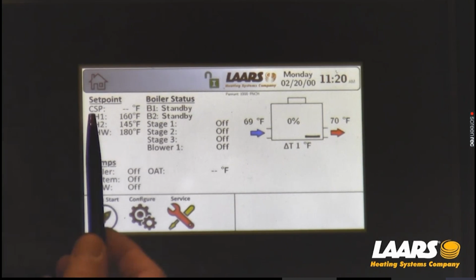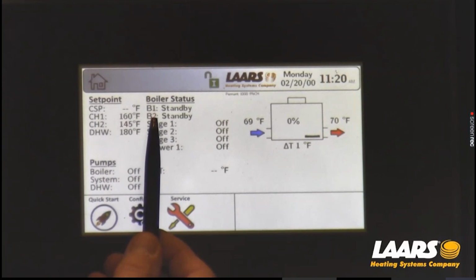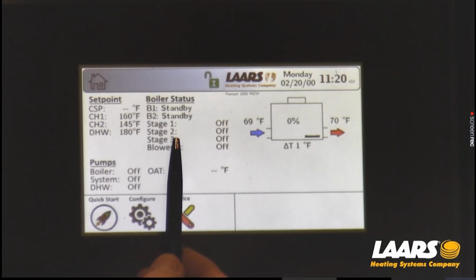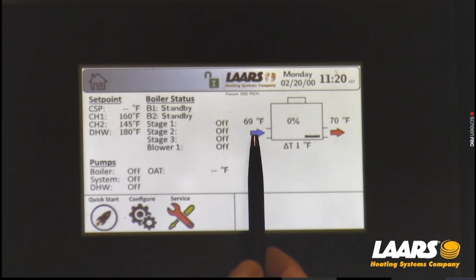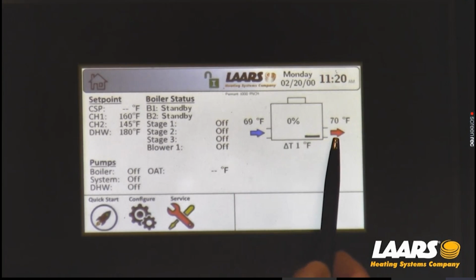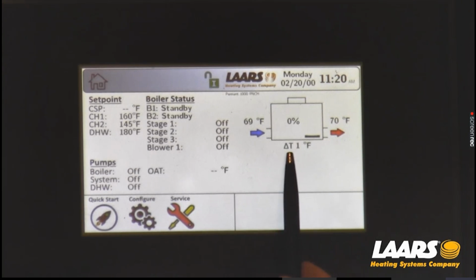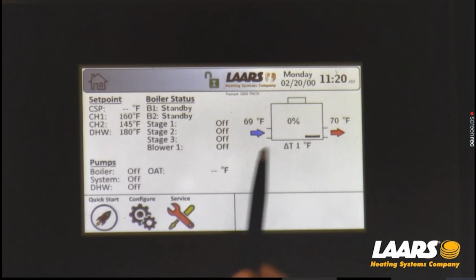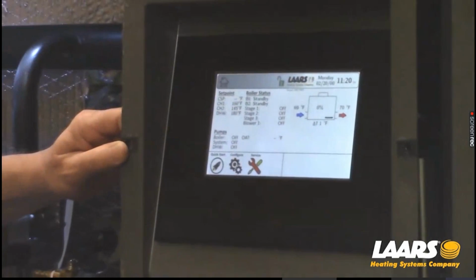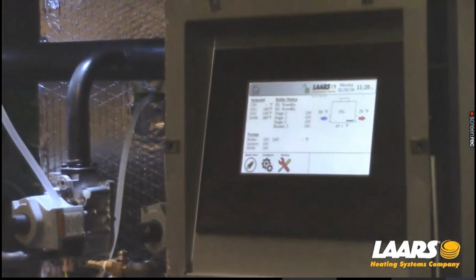So I want to give this boiler a call for heat. B1 and B2 is in standby. My stages are all off. Blower is all off. Currently, I'm showing an inlet temperature of 69 degrees and an outlet temperature of 70 degrees with a delta T of 1 degree. Okay? Boiler's firing or fan speed at 0%. I will give this boiler a call for heat.